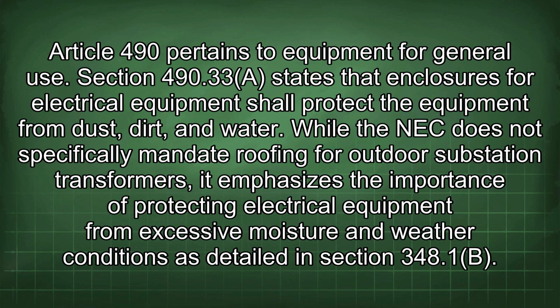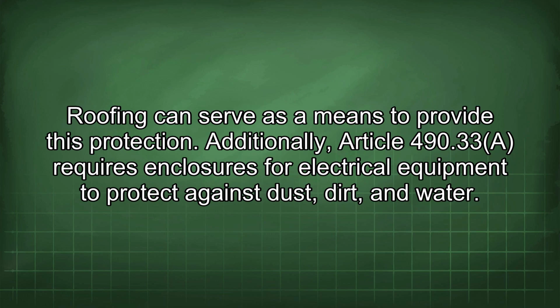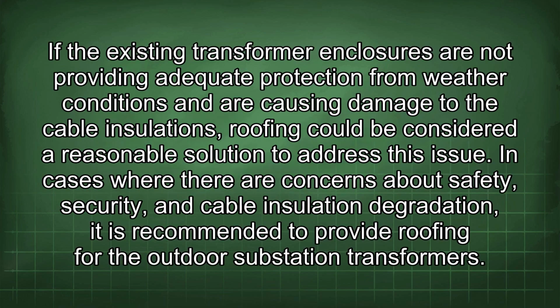While the NEC does not specifically mandate roofing for outdoor substation transformers, it emphasizes the importance of protecting electrical equipment from excessive moisture and weather conditions as detailed in Section 348.1b. Roofing can serve as a means to provide this protection. Additionally, Article 490.33 requires enclosures for electrical equipment to protect against dust, dirt, and water. If the existing transformer enclosures are not providing adequate protection from weather conditions and are causing damage to the cable insulations, roofing could be considered a reasonable solution to address this issue.